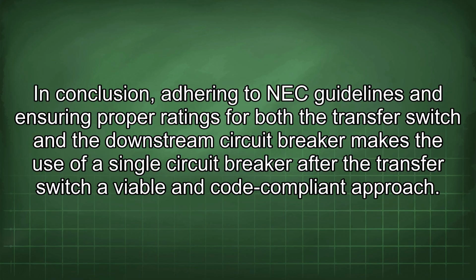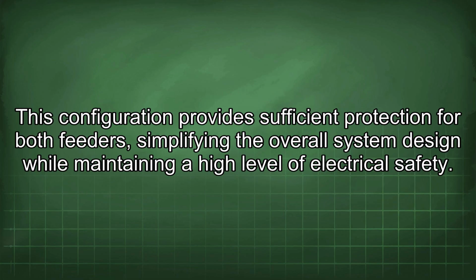In conclusion, adhering to NEC guidelines and ensuring proper ratings for both the transfer switch and the downstream circuit breaker makes the use of a single circuit breaker after the transfer switch a viable and code-compliant approach. This configuration provides sufficient protection for both feeders, simplifying the overall system design while maintaining a high level of electrical safety.